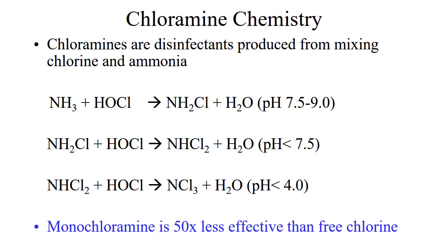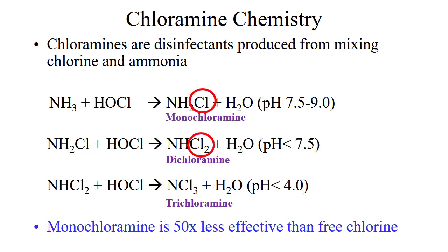Monochloramine is created by mixing ammonia into water with a free chlorine residual. Depending on the pH of the water, it is also possible to create dichloramine and trichloramine. One way of remembering the different chloramine species is: monochloramine has 1 chlorine, dichloramine has 2 chlorines, and trichloramine has 3 chlorines. These species are referred to as combined chlorine. Total chlorine is the sum of the combined chlorine residual and the free chlorine residual. The pH range between 7.5 and 9.0 is ideal for forming monochloramine. Dichloramine is not detectable above a pH of 7.5, and trichloramine is not detectable above a pH of 4.